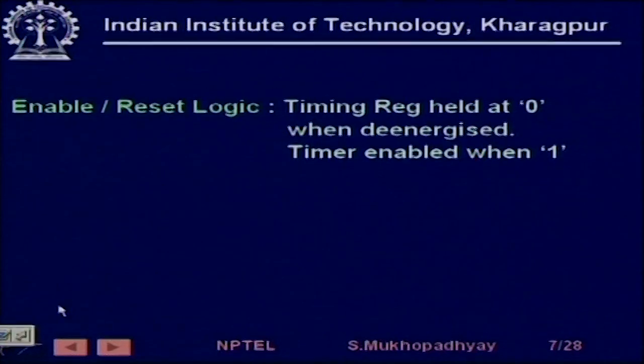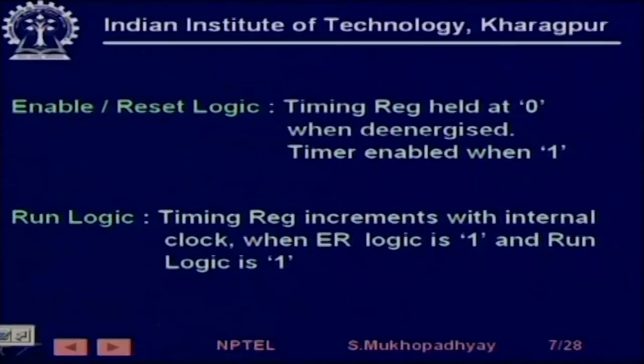To recapitulate: we have enable-reset logic where the timing register is held at 0 when de-energized, and the timer is enabled when 1 — at that point the timer is ready to receive clock pulses and increment its values. We also have run logic where the timing register increments with the internal clock when the enable-reset logic is 1 and the run logic is also 1. This is the basic timer.